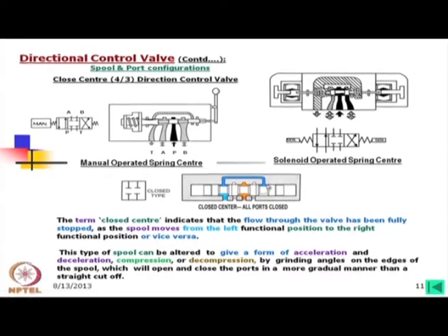But it is very difficult to grind these edges properly, because this is inside the valve body, this bore. Rather we change the design of the edge. Now, if we provide these chamfers or make it round, then the port will open and close in a more gradual manner than a straight cut off, and sometimes it is essential, because the straight cut off will give a shock to the system.